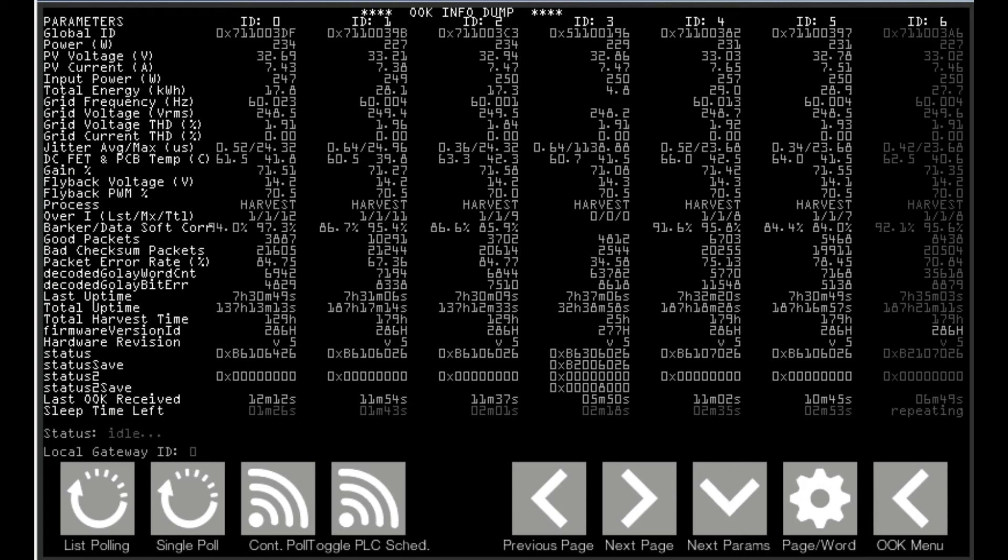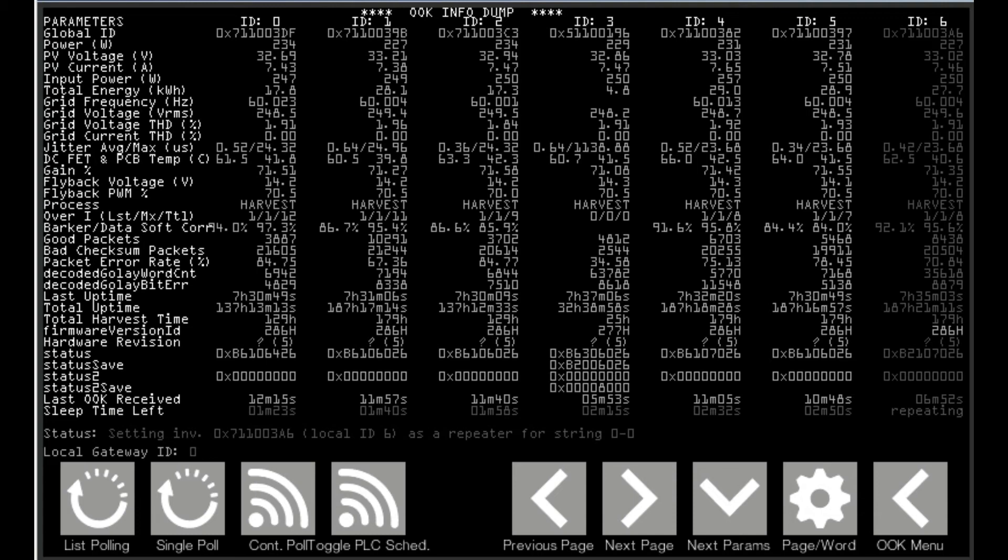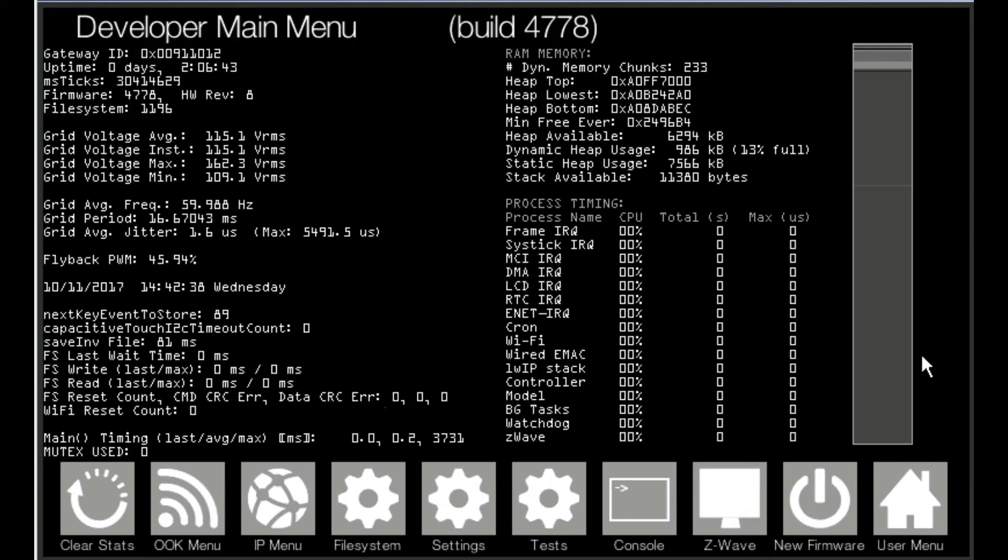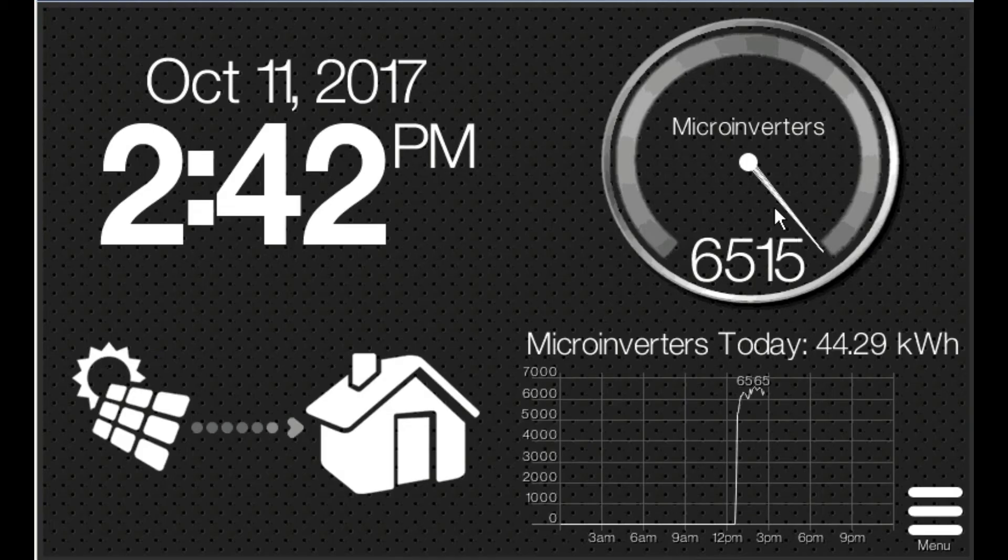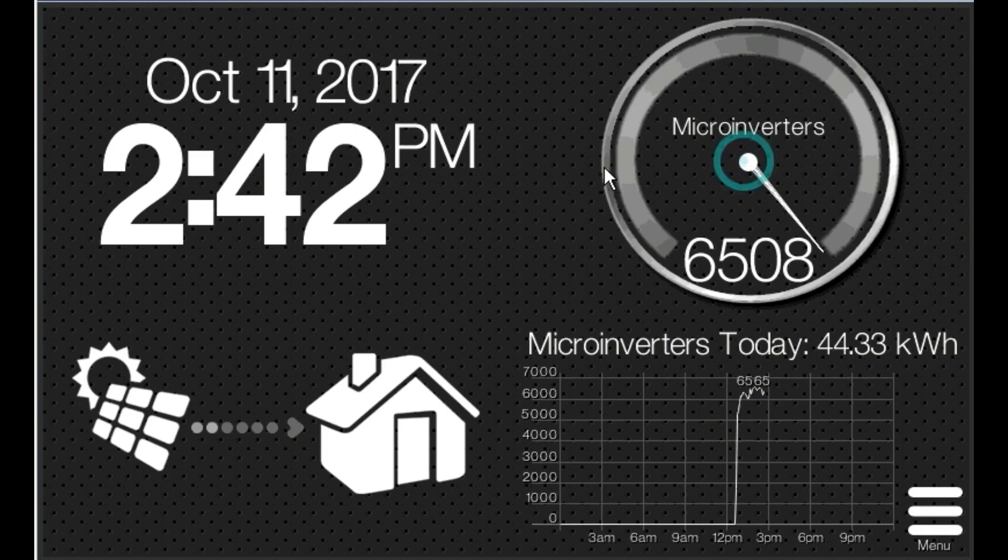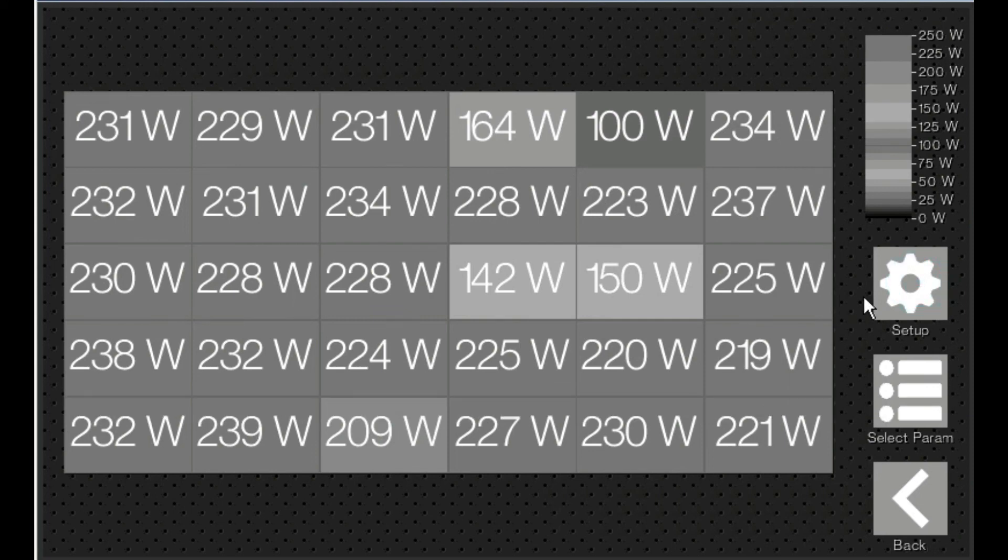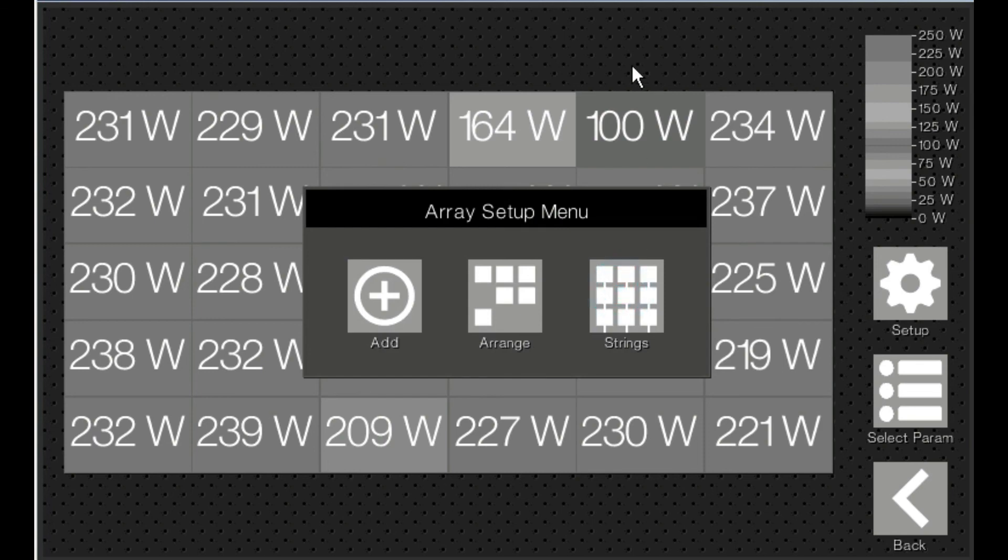First always resume toggle PLC scheduler to put the automatic polling back on. But the way unit 6 has been assigned to the repeater is up here at the top level. And what we have is we can click inside and look at the array. And from the array view we can hit set up. And now there's the notion of strings. And the strings are logical clusterings of inverters that are polled together.